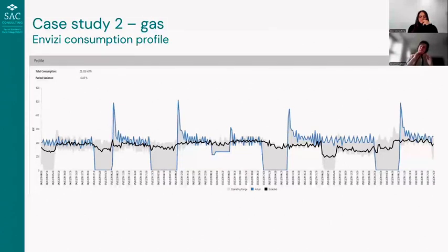Now, you can see there are these drops, not quite regular. I think once or twice the engineers actually forgot to switch the boilers off, which is fine, they've never had to do it before. So on about 2 days they haven't switched them off, and we still saw the 16% reduction, even with these 2, 3, 4 nights when they weren't switched off.